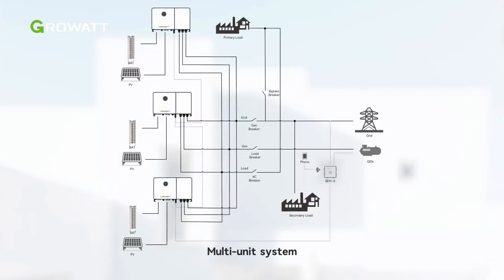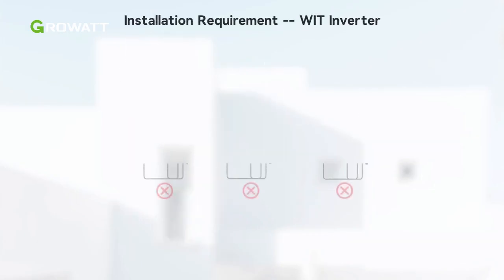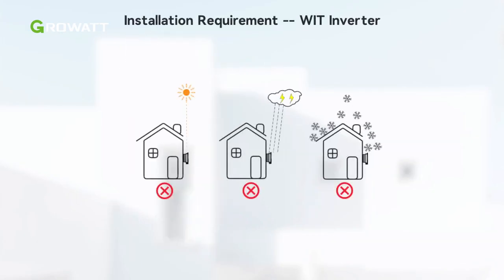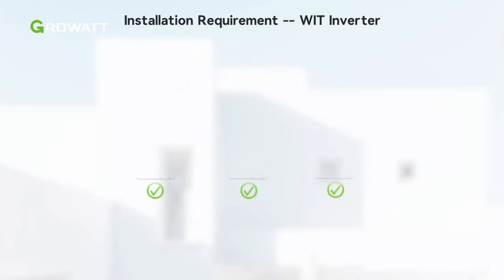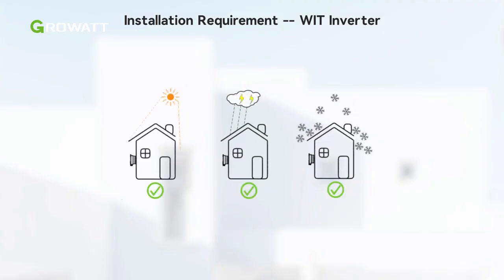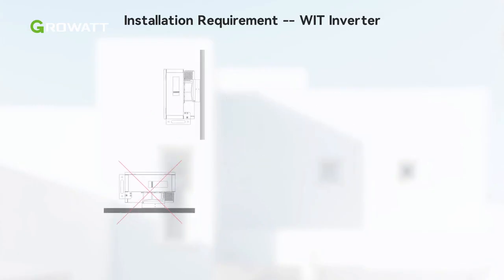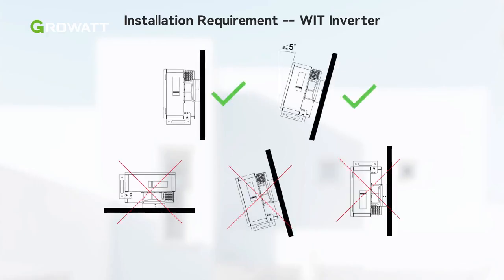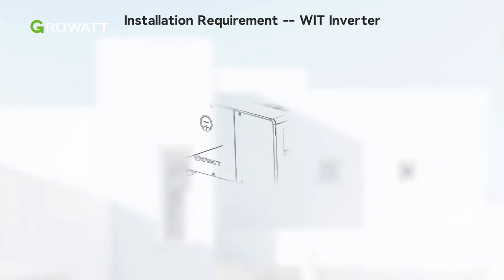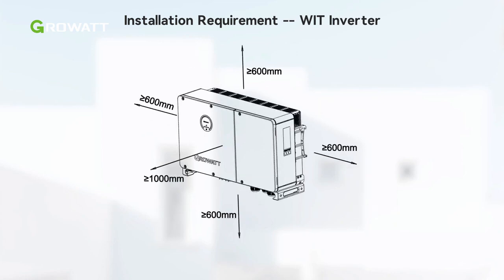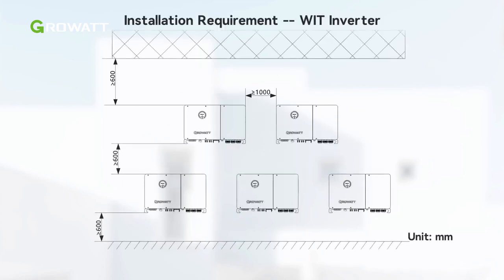capacity. When installed outdoors, to ensure optimal performance and long service life of WIT-XHU inverters, it is best to avoid direct sunlight, rain and snow, and to install an awning over the unit. The WIT inverter can be installed vertically or backward tilted with a small angle. Please reserve enough clearance around the WIT inverter to ensure sufficient space for heat dissipation and operation.